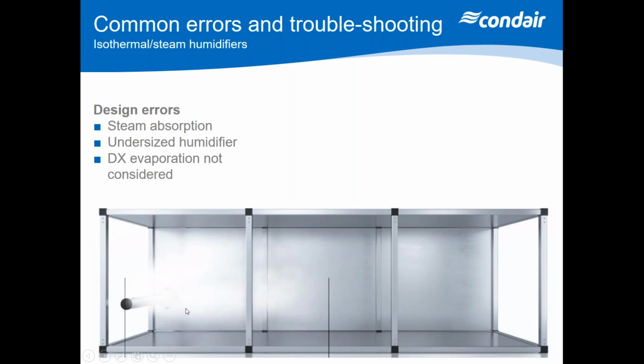Also, we're going to see sometimes that people are opening up fresh air dampers. Now, we're going to select on fresh air supply, how much fresh air is going into the system. If someone now is looking at opening up fresh air, especially now with the new stage requirements, that you're going to see that more fresh air is being required now in these areas, that's going to have an effect on the humidifier. They make the humidifier undersized.